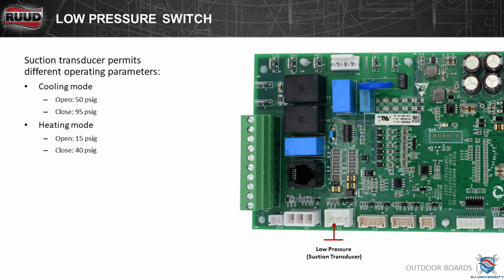Your low pressure switch has 2 different settings, and the reason they've gone to this is because they've used a pressure transducer on it versus an actual switch. So in cooling mode, it'll open at 50 and close at 95. Heating mode is 15 and 40. So it has 2 different parameters that it can look at because they're using a pressure transducer, not just a common pressure switch. And here's where your low pressure suction transducer connects into the board.